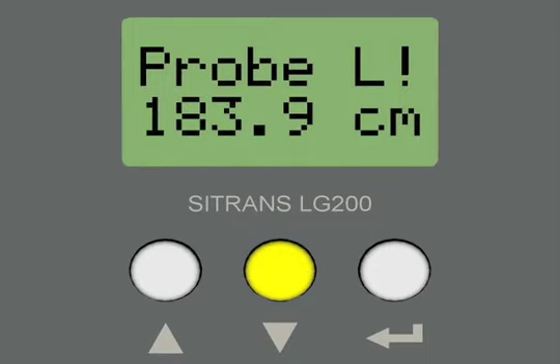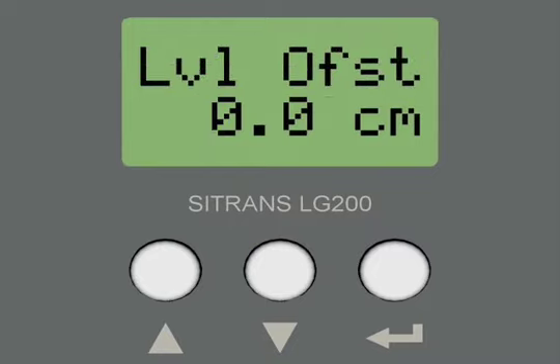As the value approaches the desired 60 centimeter length, release the down arrow key. Then use the up and down arrow keys to trim the displayed value to show the desired length. Push the Enter key to set this parameter. The next parameter is the level offset parameter. We do not need to adjust this parameter for our application, so we can continue to the next parameter.